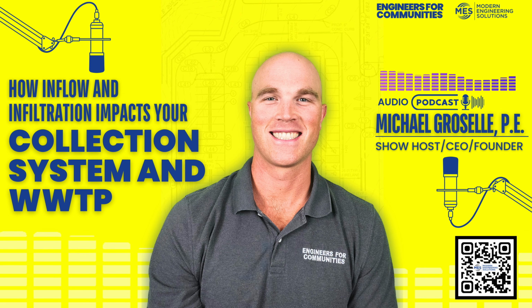So you can see here in the past, they've exceeded it. They probably had some really, really bad I&I back in 2019. They had a blip here most recently, May of 2021. And then they've been slowly hovering just below that planning limit, but still safely below it. On the right here, you'll notice that there's no data since November of 2022. The EPA is pretty slow at getting that data updated in this portal. So don't think that you just had no flow those months.